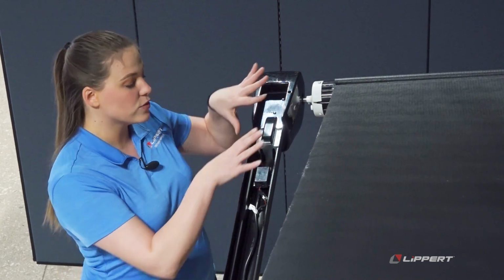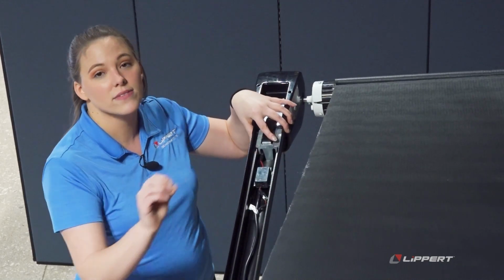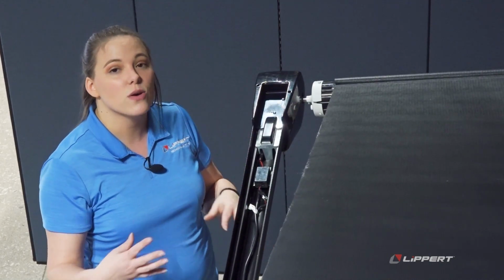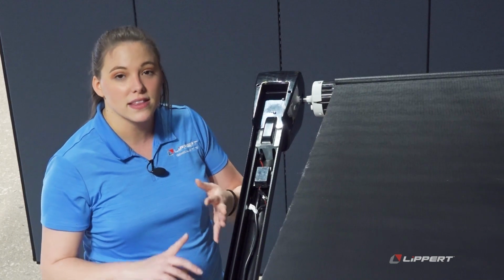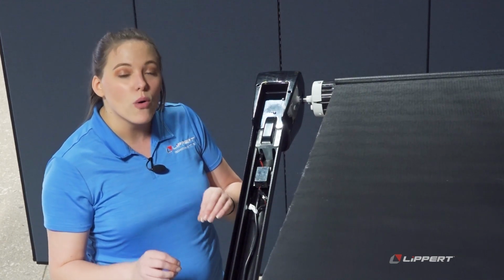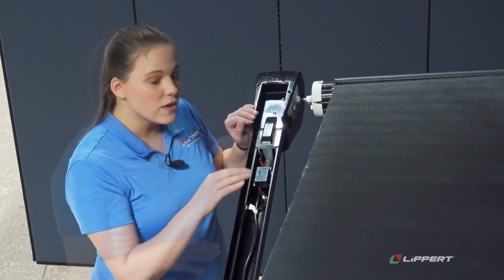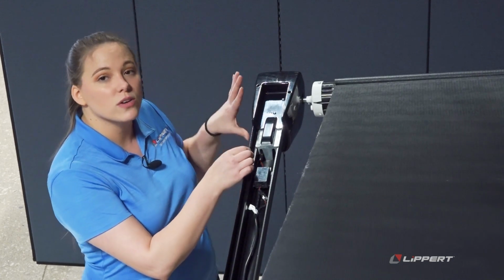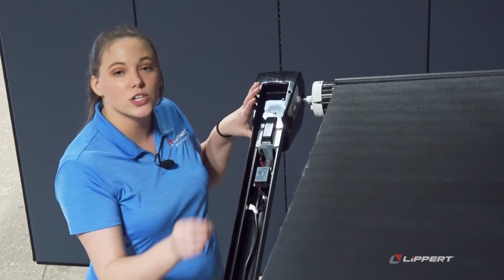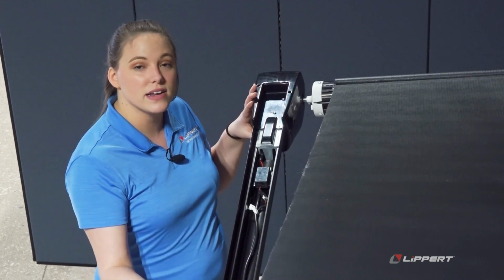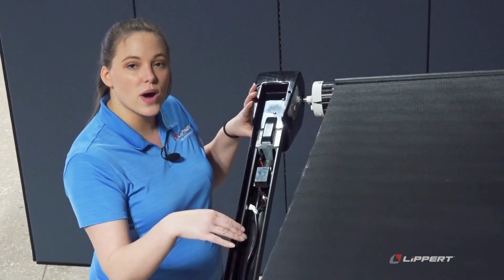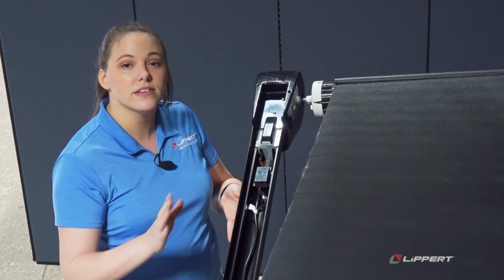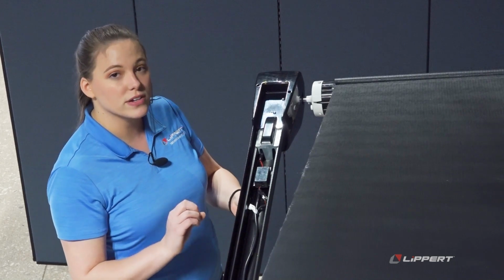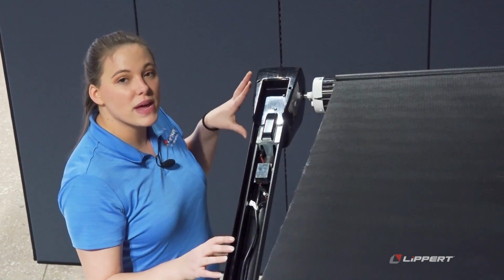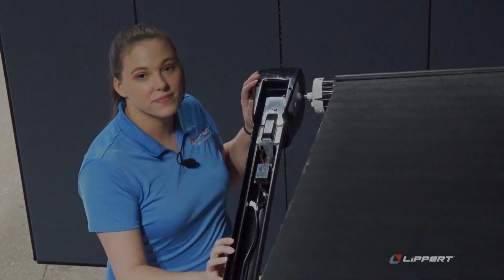To do that, you would have to hold your multimeter here and then have somebody else press the extend or retract switch either at the interior of your unit or at the touchpad. If you are getting that current, but your motor is not functioning properly, that shows you that the touchpad is sending the signals through the wire harness and that the wire harness and touchpad are in good condition, but your motor may need to be replaced.